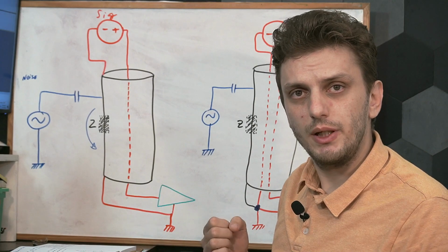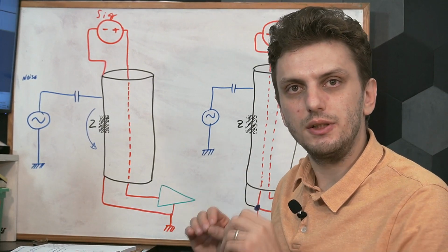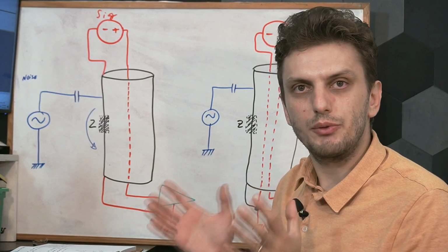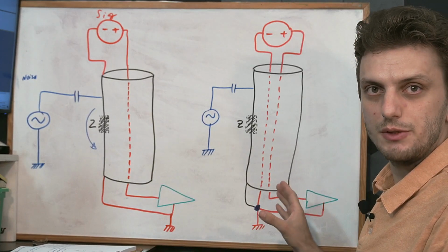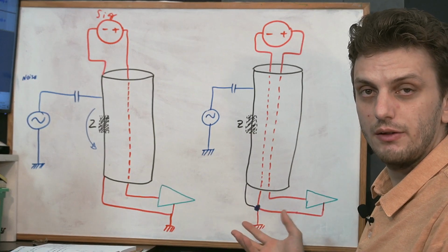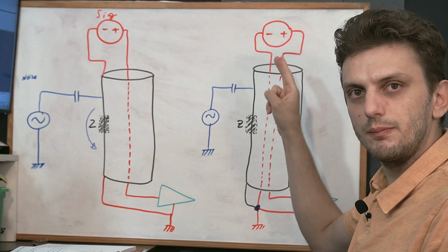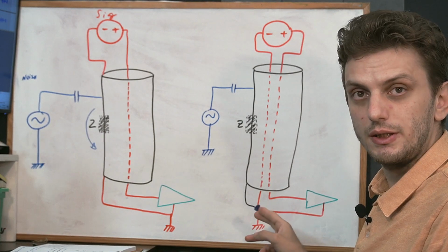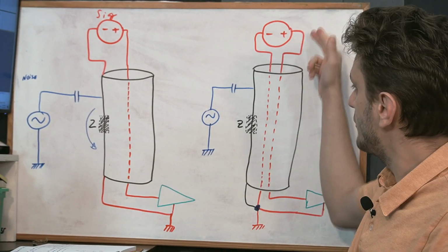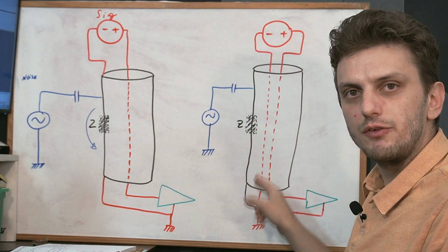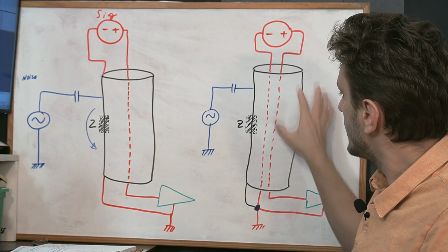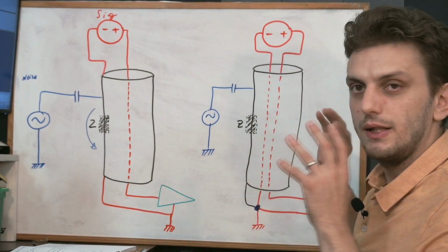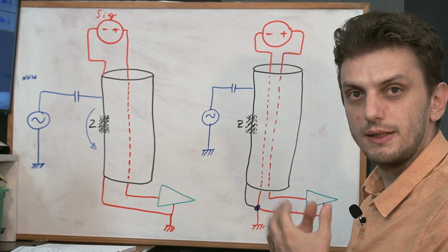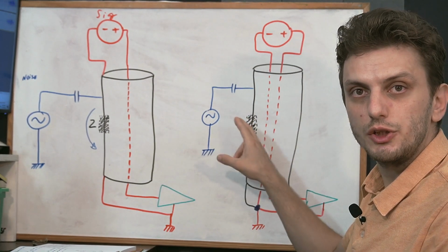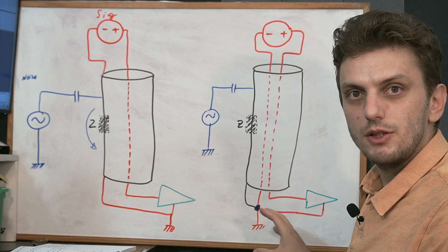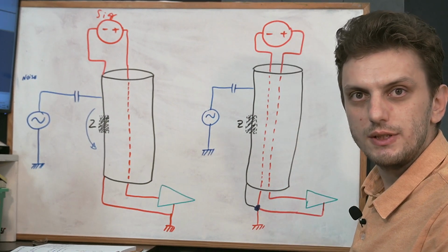So the solution to this is to use an extra shielding layer, or in other words, separate the grounds. What I have here is basically the same circuit as on the left side, the difference being that my signal now travels through my shielded cable on two wires. I have my positive signal line, but also my ground pin. My shielding layer is an added-on layer that only acts as a shield. This way, whatever voltage drop happens on the shielding does not get added on top of the useful signal.